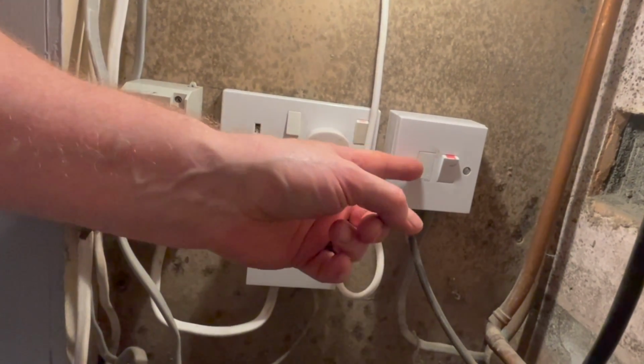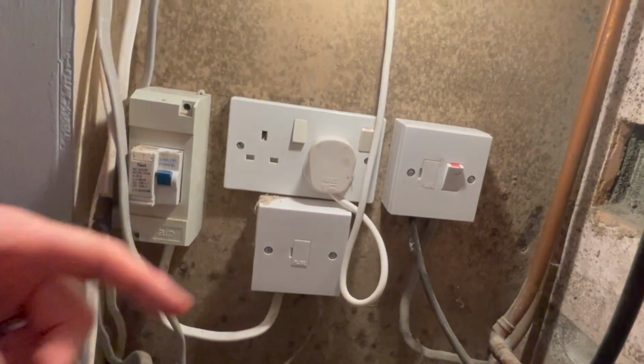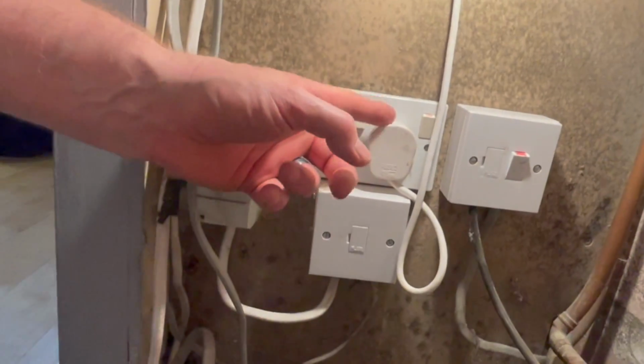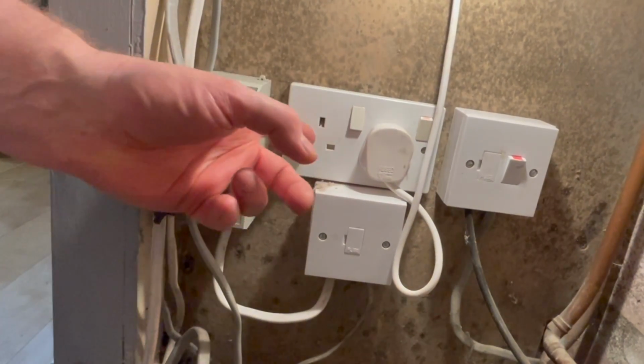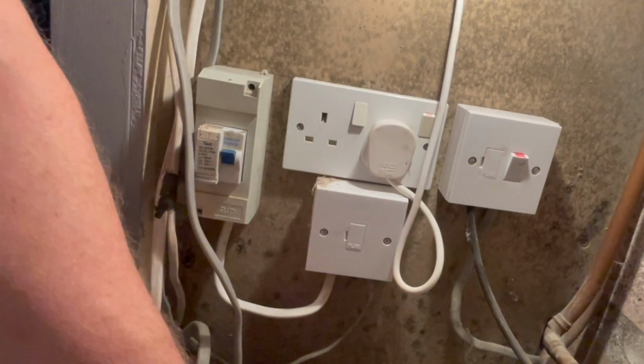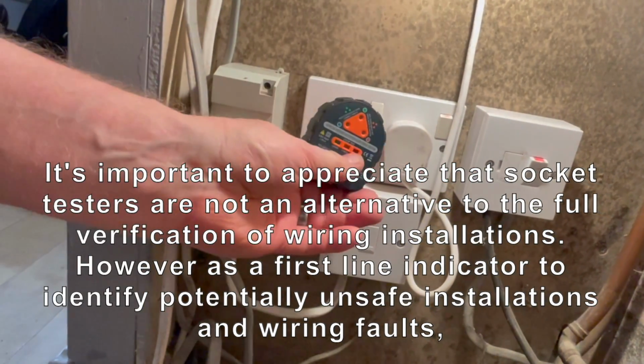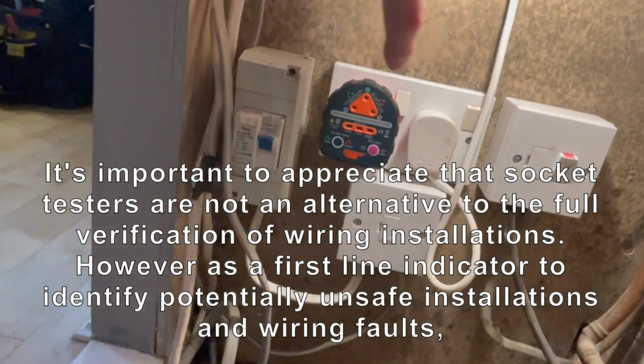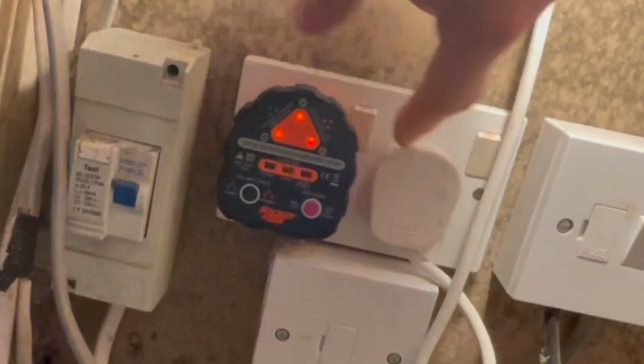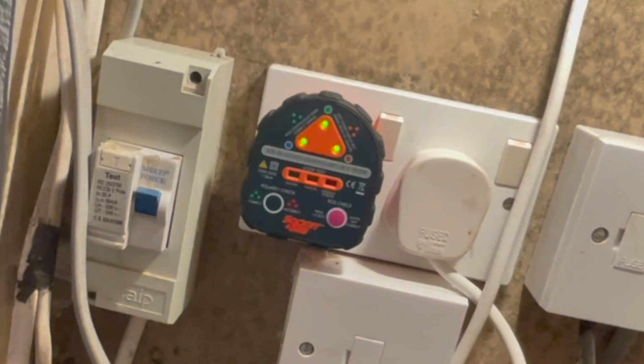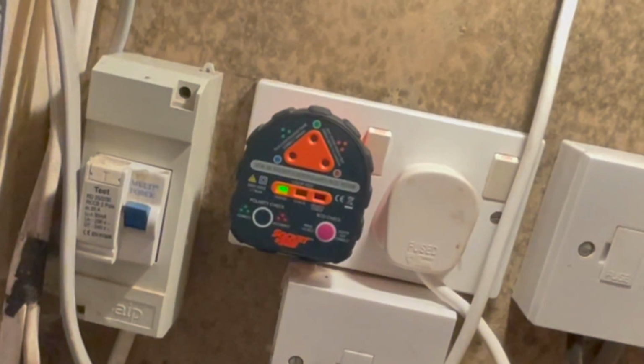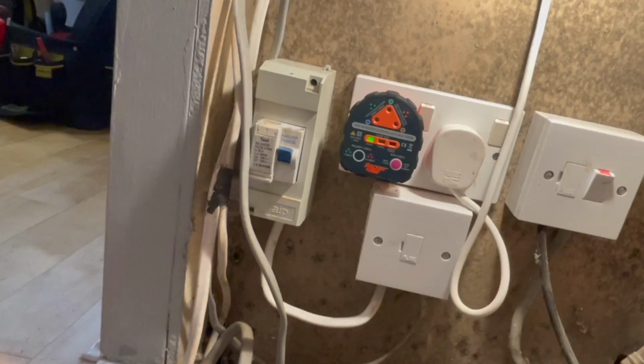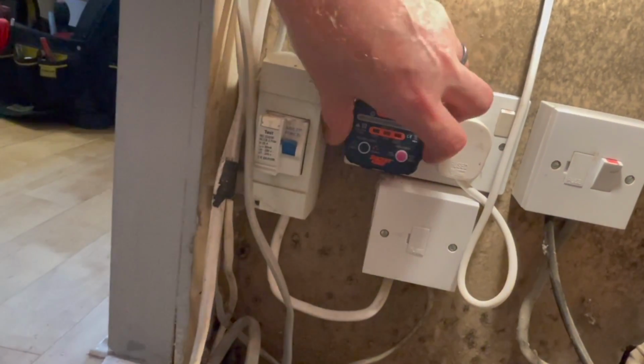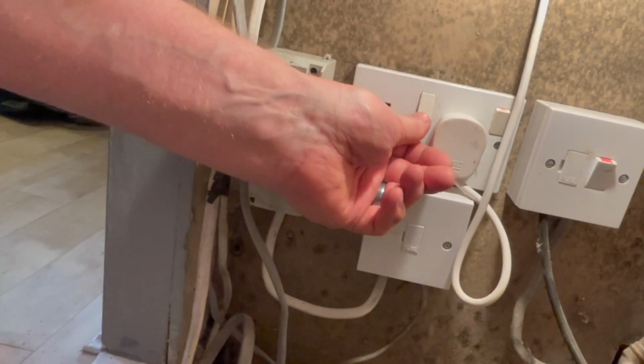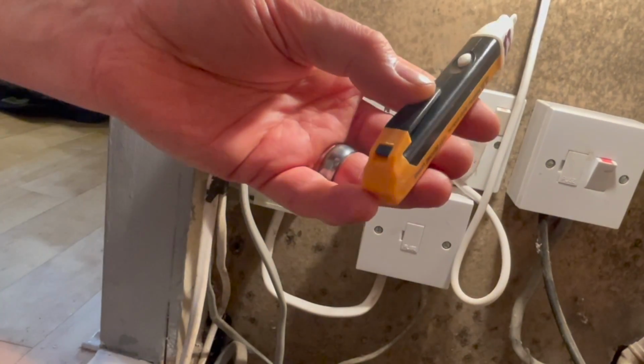Now, the boiler is wired into this fuse spur here. We will check the fuse in a minute, and we can see this light is wired into this socket here. Now, what I'm going to do is check the socket is wired correctly by using my socket tester. This has also got an earth loop impedance tester to see whether we've got an earth or not. So I'm just going to flick it on, and we should get 3 green lights here, which we have, and then we should get a green light here to say everything's correct with the earth loop impedance test. So that's correct. I now have a known supply to test my non-contact voltage indicator.